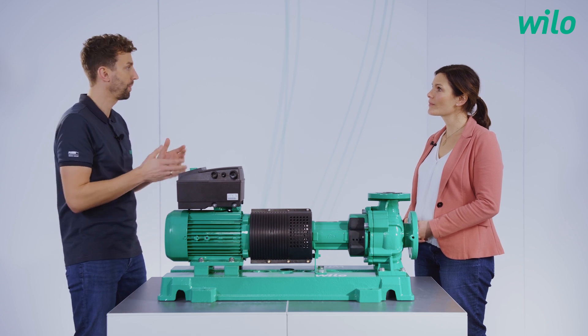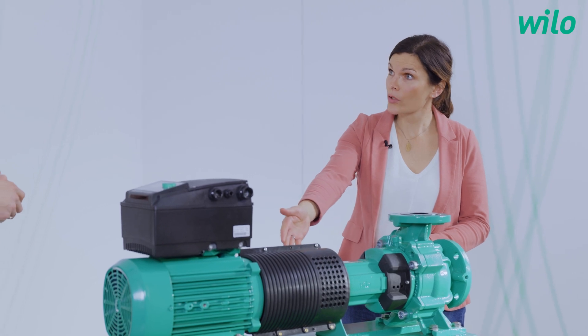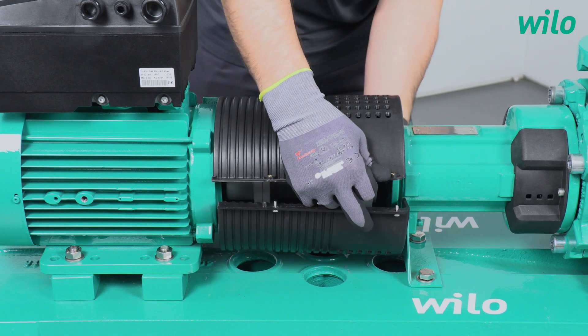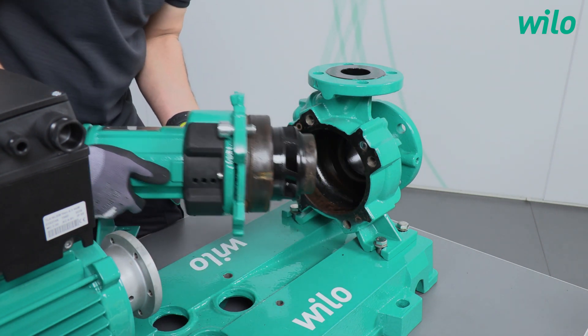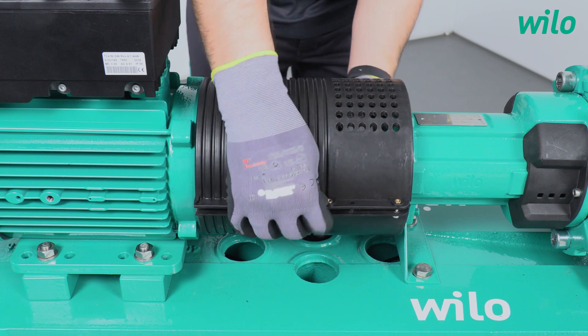Maintenance is a big challenge for the plumber installers. This is a norm pump and due to the special design, we have the spacer coupling which you can see here. You simply unscrew the screws, put the protection away, and then you can remove the coupling below. After taking away these screws, you can simply move out the unit and exchange the mechanical seal inside. And the big advantage is that the hydraulic and the motor just stay there — they don't need to be moved or realigned. So this can even be done by one installer, very fast and very easy.